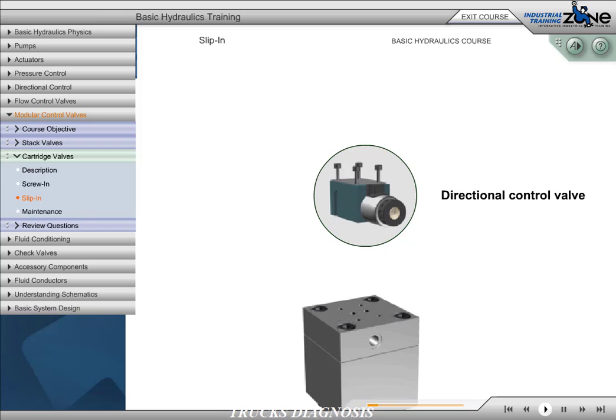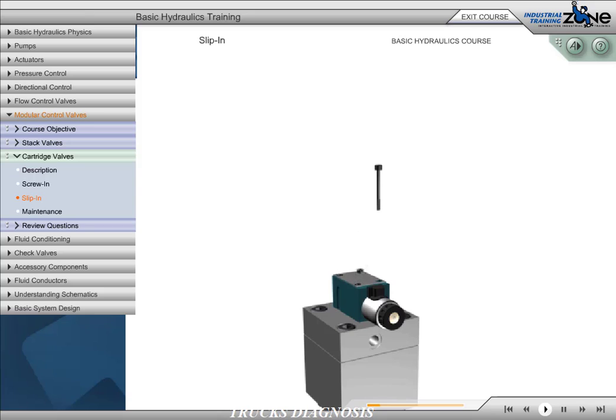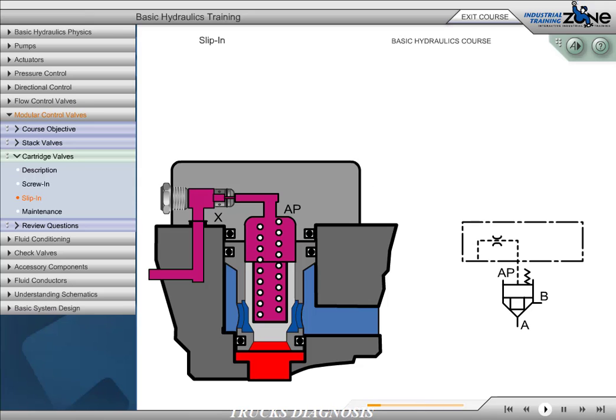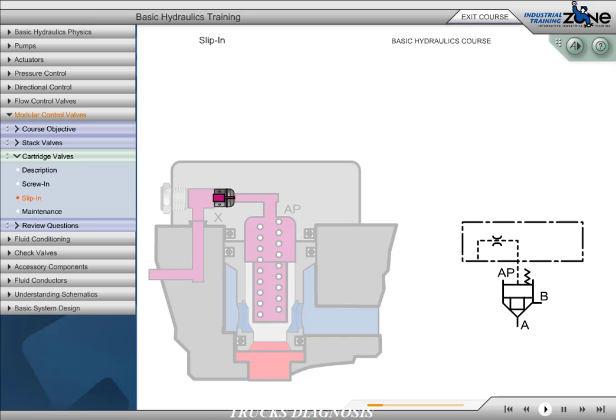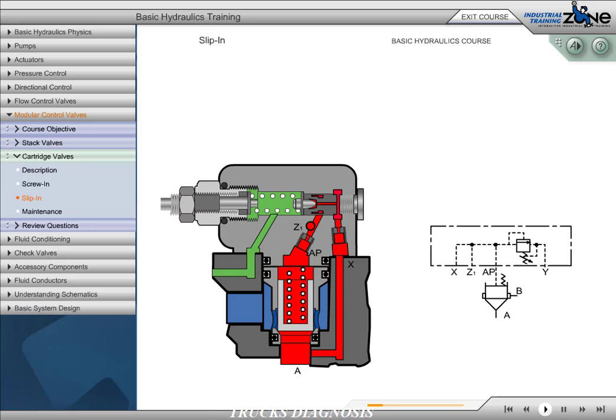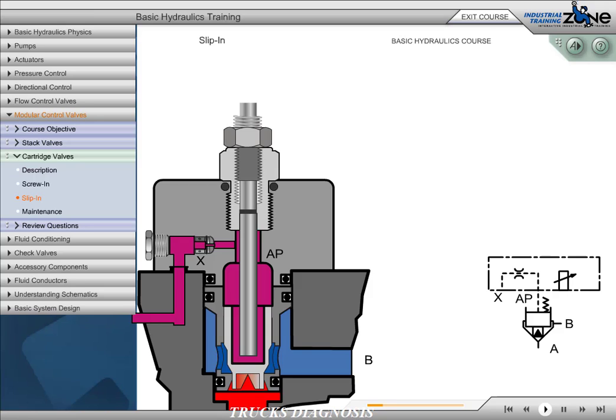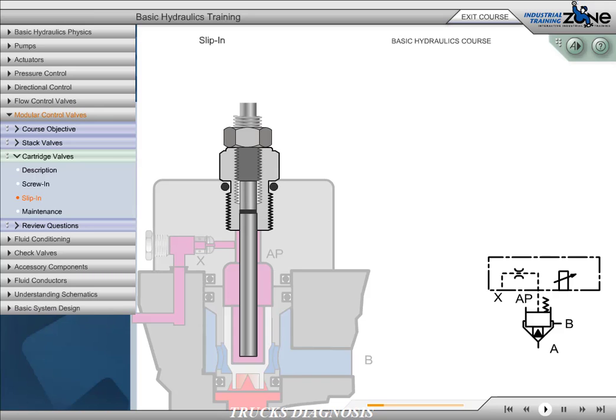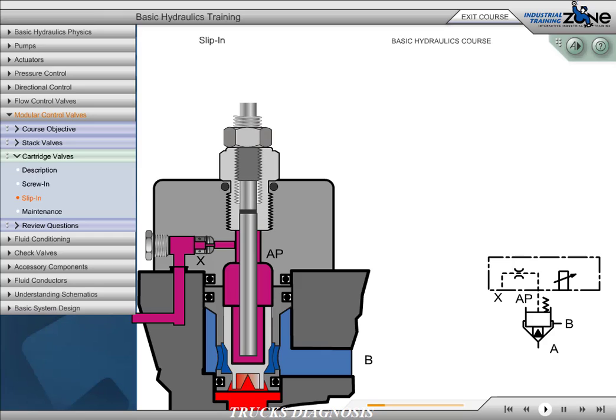A directional control valve used to control the function of a slip-in cartridge can be mounted on the surface of an interface cover. Some cover assemblies also contain other options such as orifices, stroke adjusters, or a direct acting relief valve to create additional valve functions. These control covers function like a pilot section of a two-stage valve, while the slip-in cartridge functions like the main stage of a two-stage valve.